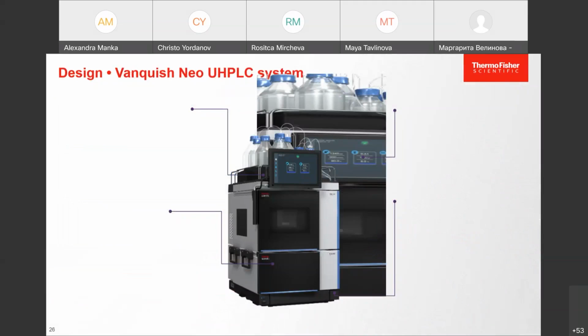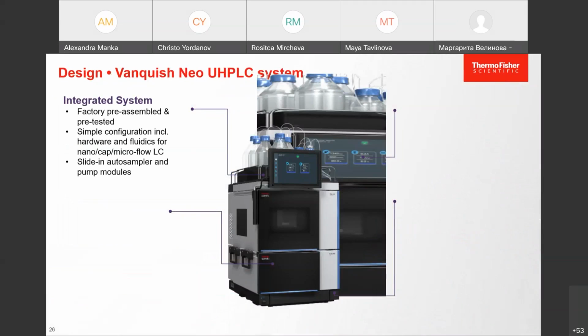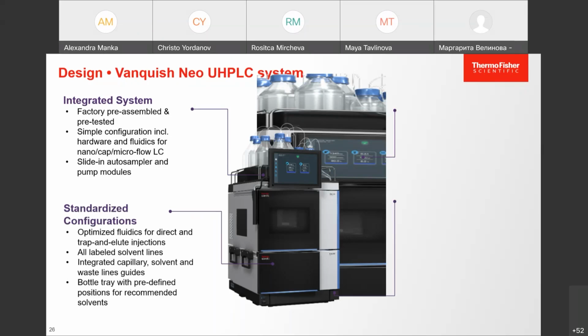So this is how this system looks. I'm sorry, the picture in the background shifted somehow. So it's an integrated system. It's factory pre-assembled and pre-tested. So you get a system that is made of modules, but you get it out of the box as an assembled system. It has a simple configuration for nano, capillary and micro flow LC. And as said, it has the slide-in auto sampler and pump modules that we have on all Vanquish systems already. You have this standardized configuration with optimized fluidics for direct, trap-and-elute injections.